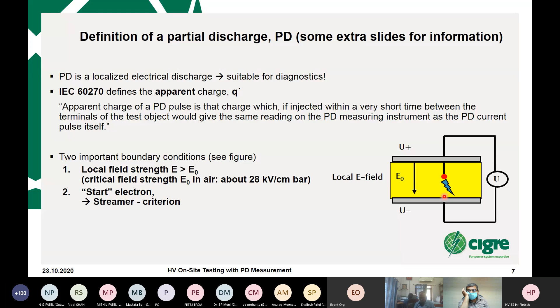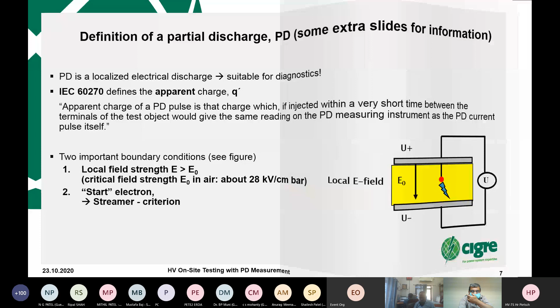And of course, you need a local electric field, and then a defect. In this case, for example, a gas-insulated part. Then you have a discharge, and in a homogeneous field, it will directly break down and so on. If it's inhomogeneous, then this can serve as a diagnostic, and this is very often used. And these are, for example, some pictures, double exposure. That's the reason you can see it like here. So you have high voltage applied here, and this aluminum tube, which has some scratches, and you see the localized PD. They are in the region of 30-40 picocoulomb. And if the test lab is dark and all lights are switched off and your eye is adapted, you will see it like that.